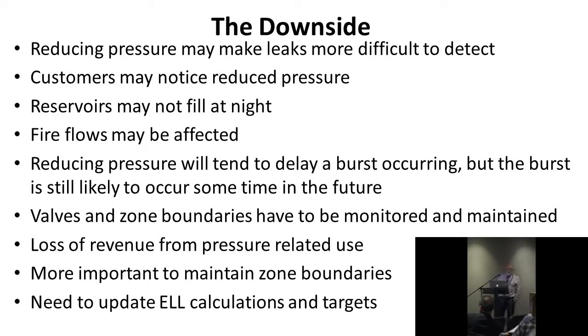Slight downside, you reduce pressure, which may make leaks more difficult to detect, particularly on plastic systems. Customers may notice reduced pressure, and you may have an increase in customer complaints, but you should train your guys well to manage that. Quite often, people have experienced high pressure in the past and may have actually screwed their stopcock down. When you then do pressure reduction, they get quite poor service. You guys should go out and have a look and check that their stopcocks are open.